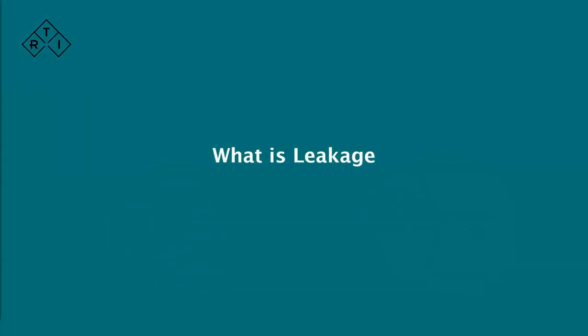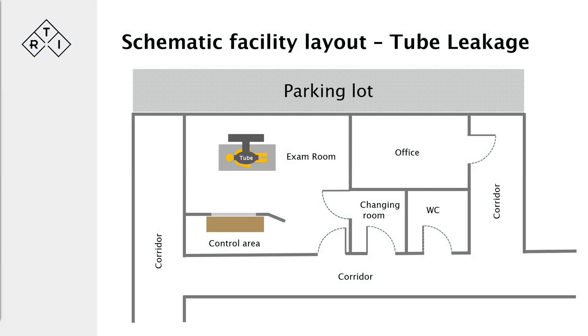Let's take a closer look at leakage. Leakage arises because X-rays are emitted in all directions from the target or anode, not just in the direction of the primary beam. Although the tube housing is heavily shielded, some leakage radiation can still be transmitted. That is one of the things we are interested in measuring, to make sure leakage radiation is within permissible limits.